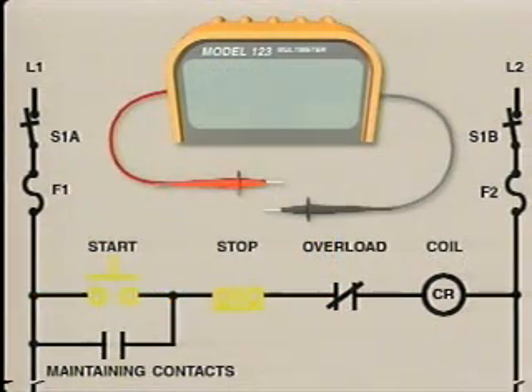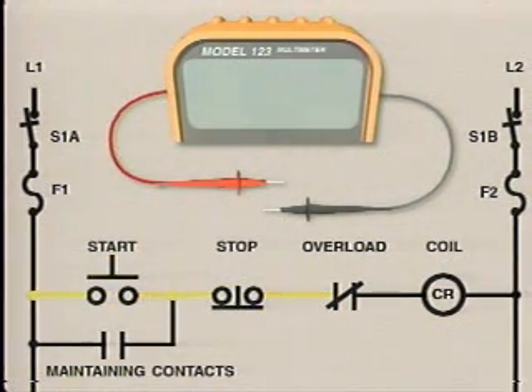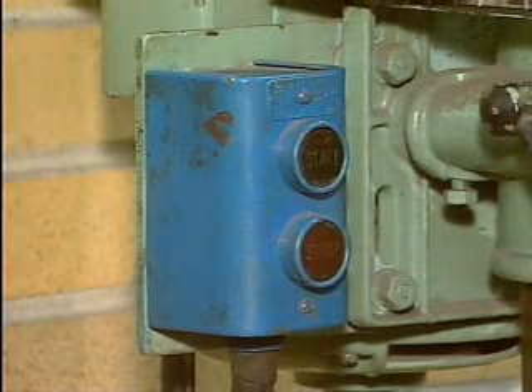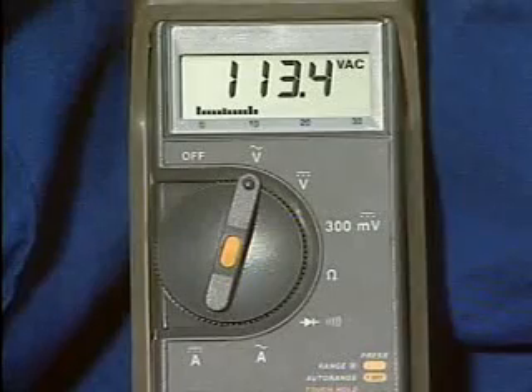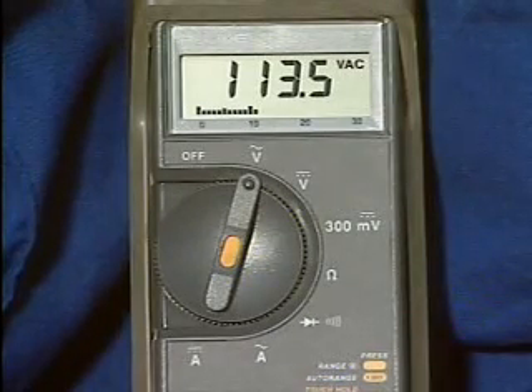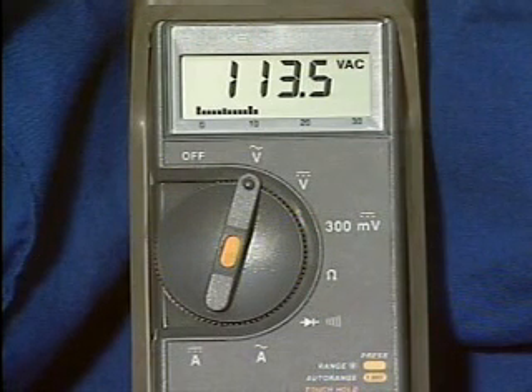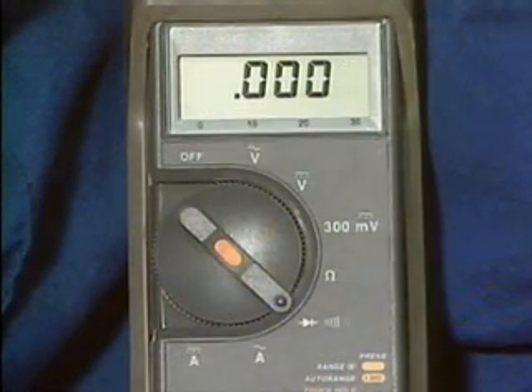So the cause of the problem is either in one of the two push-button switches or in the wiring that's connected to the switches. Since it's more likely that the problem is in one of the two push-button switches, they'll be checked first. The electrician can check the switches by making voltage tests with the power to the circuit turned on, or by making continuity checks with the power turned off.